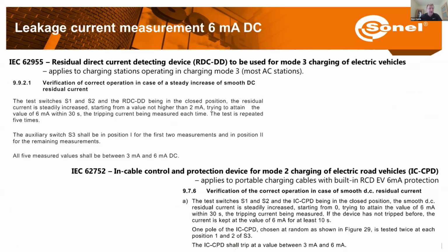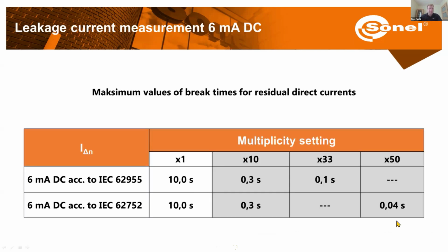And here the international standard IEC 62955 describes how to test these protections. This standard is for mode 3 charging, so wherever we have a public AC charging station. But for mode 2, so when we have these charging cables with the box with breakers with the RCDs, the IEC 62752 applies. To simplify how to perform the testing for each standard, we're going to have 6 milliamps DC current, and depending on the standard, we need to multiply it by 1, 10, 33, or 50 times. And the standards define how quickly the RCD should work. So you can see the requirements here in this table.